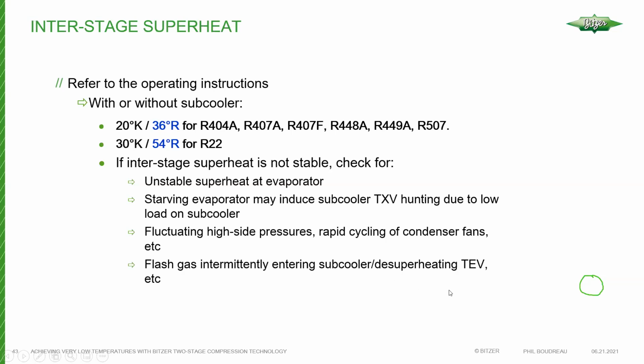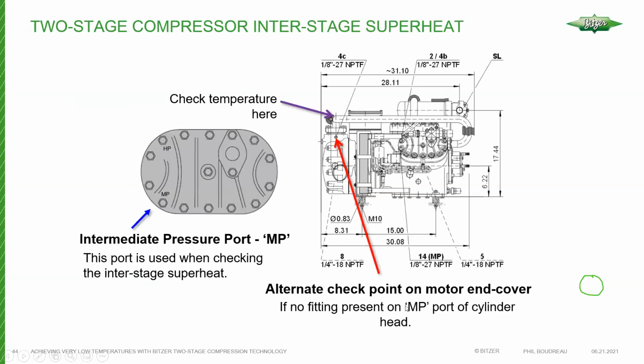I'd be happy to share some of this material with you if you send me an email afterwards, if you want to read up on it on your own, especially considering I'm going through some of this material pretty quickly now. When you're checking your interstage superheat, you want to check the temperature at the point where the interstage enters the motor barrel, and you want to check the pressure at an MP port on a cylinder head. Generally, this would be on the high stage head.